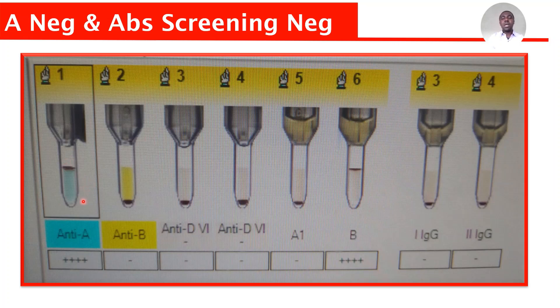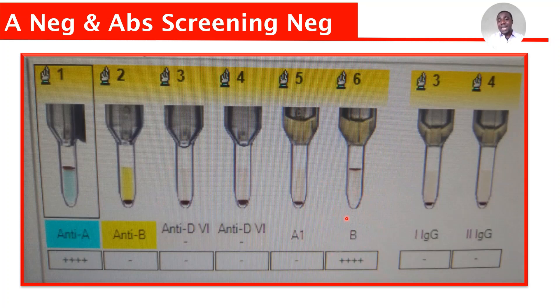Let's look at the interpretation properly. Remember that antiserum is embedded in the card. What we do here is card grouping and card antibody screening. In the card grouping, you can see anti-A, antiserum A, antiserum B, and antiserum D — that is what is embedded in columns 1 to 4. When you come to the A1 and B wells, there is nothing embedded; it's just a gel. The analyzer will take the patient cell and put it in the cell well, A cell in the A cell well, and then add the patient plasma.